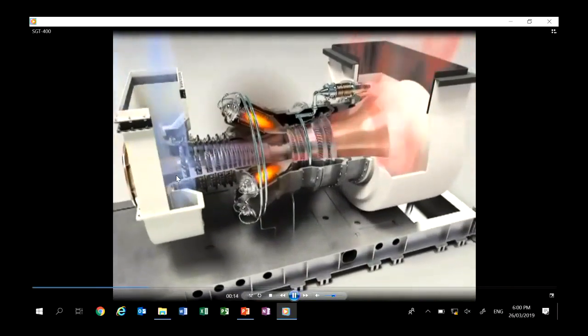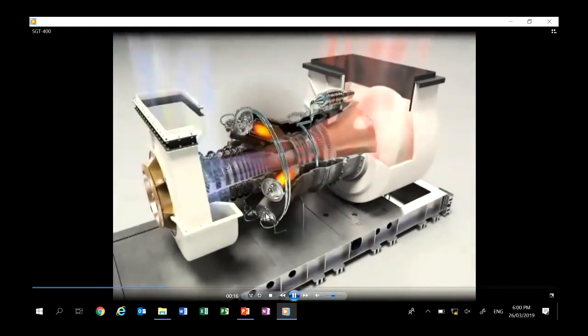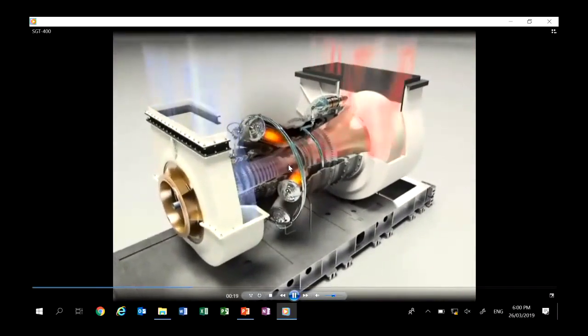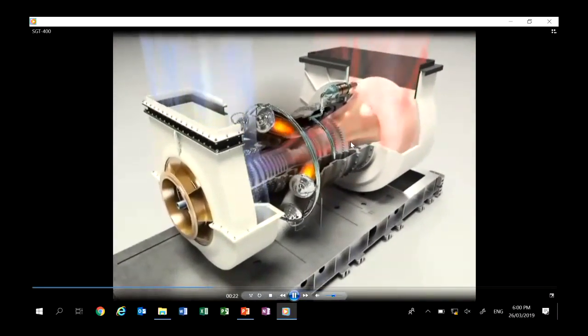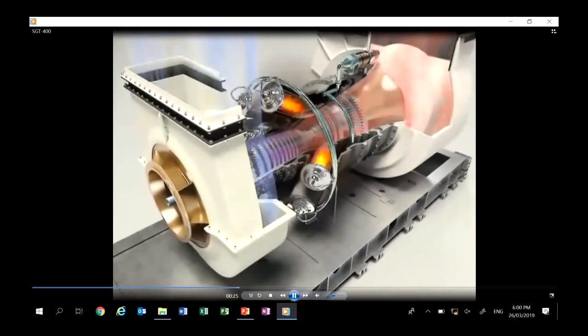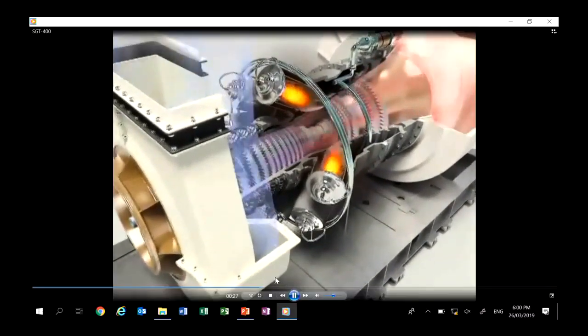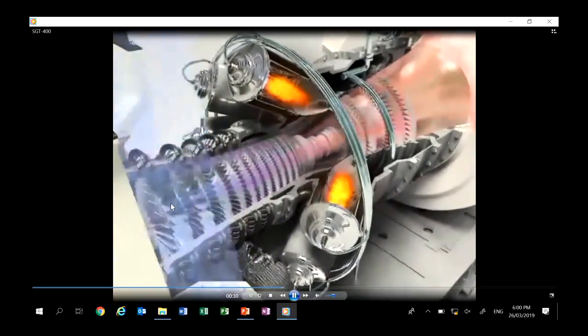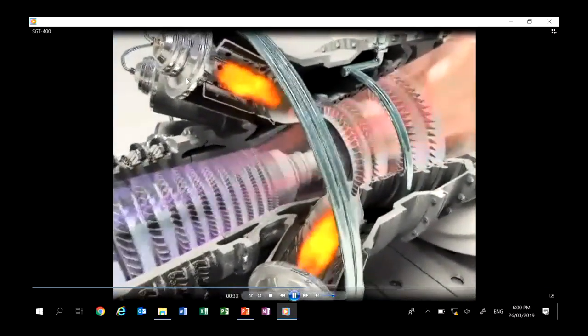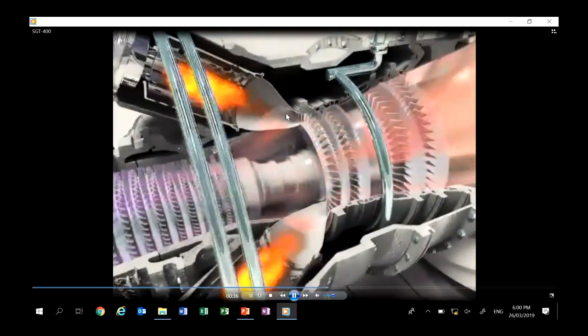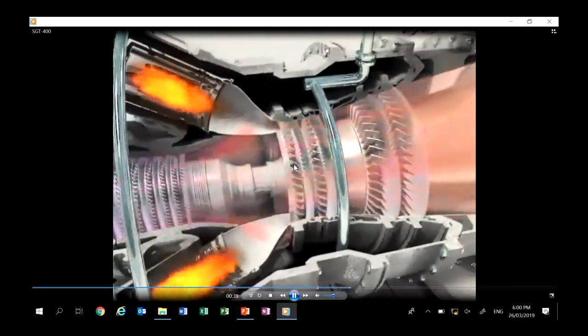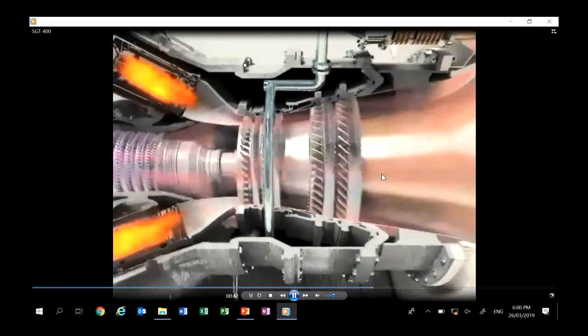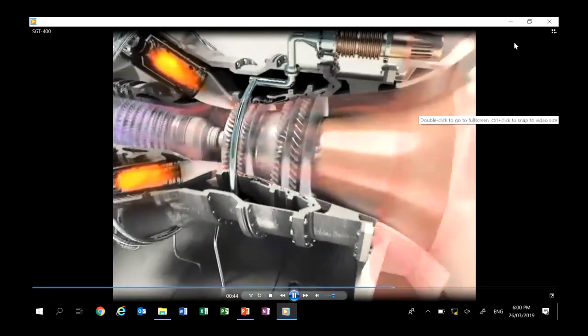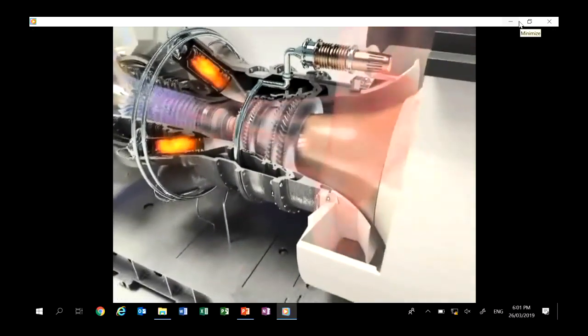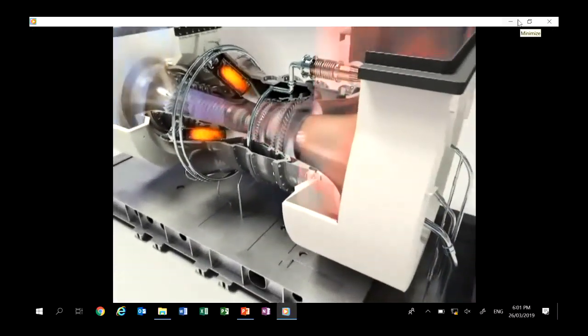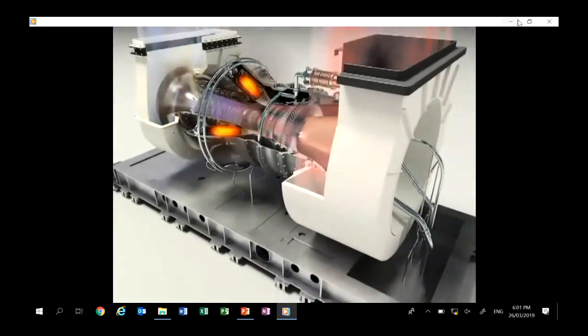The air is being drawn into the compressor here. There are, I think, 6 or 8 combustors burning natural gas, and then the gas is expanded through the turbine and exhausted up here. So this video takes us through. You can see how this thing works. Cold air is coming down here, being compressed, then channeled back around into these burners, burnt with natural gas. The gas expands through this annulus thing, in through the 4 rows of turbine blades, and then out and up into the exhaust. So I quite like this. This is quite a simple gas turbine. Every gas turbine works something like this.